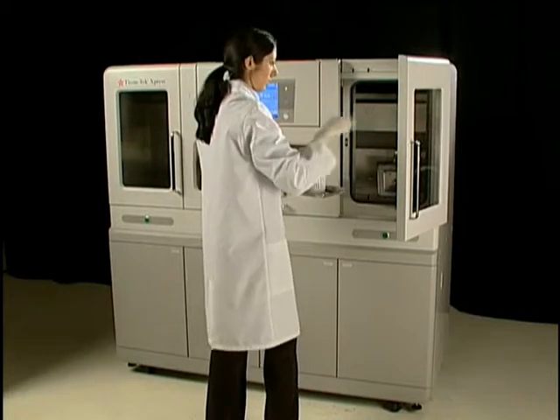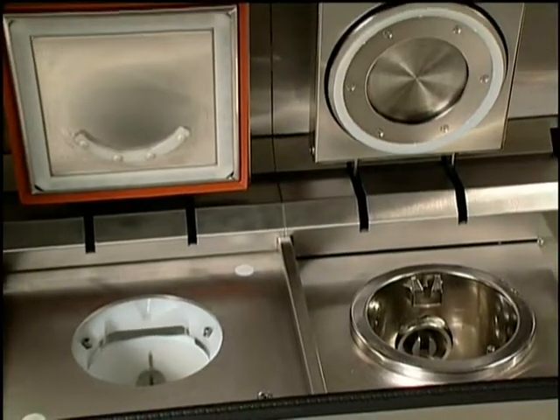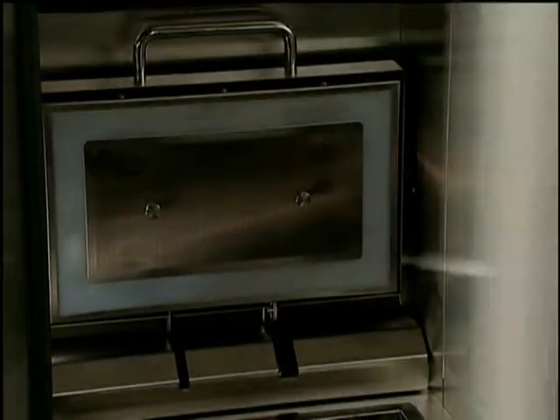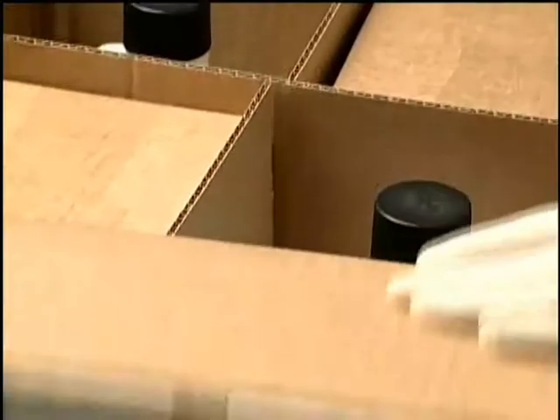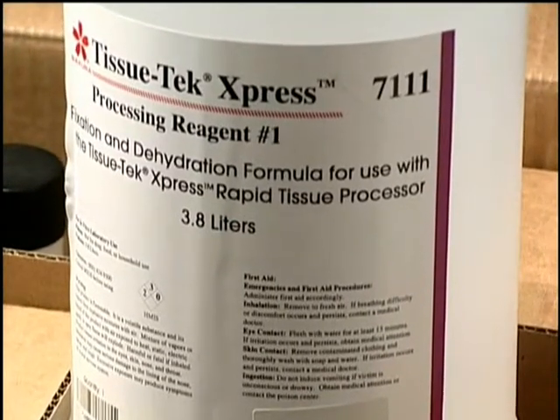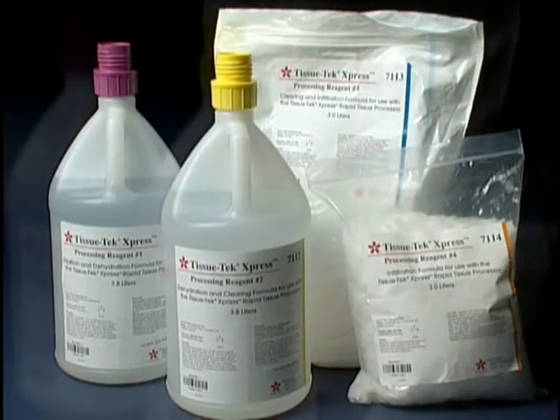One million specimens processed by the Xpress — made possible thanks to a novel reagent system using only four onboard reagents, a unique patented microwave technology, and proven vacuum infiltration techniques. These enable the pathologist to receive results that parallel those seen in overnight processing. The use of these non-formalin and non-xylene reagents in the Xpress processor ensures that laboratory staff has less exposure to hazardous chemicals. Overall reagent volume is significantly reduced by approximately 80%, enhancing safety and providing significant cost benefit to laboratories.